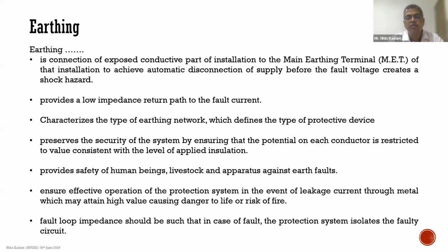Let us also understand, because people use the words interchangeably, like earthing, earth, grounding, and so on. So what is earthing? Earthing is basically a metallic conductor connecting the exposed conductive parts of any equipment to the main earthing terminal, which helps us to automatically disconnect the power supply in case of fault. It is also providing a low impedance return path to the fault current. It also helps us to define the type of earthing network that is made available at the building premises, and what kind of protective devices have to be used based on the type of earthing network available in the building. It also prevents shock to human beings and also fire in case of livestock when there are earth faults.